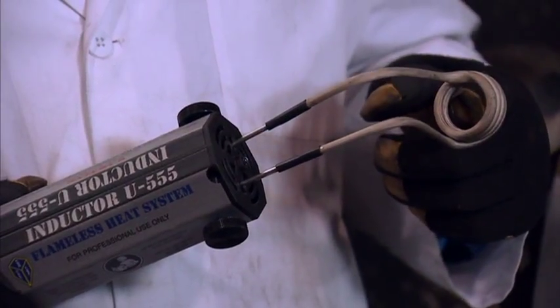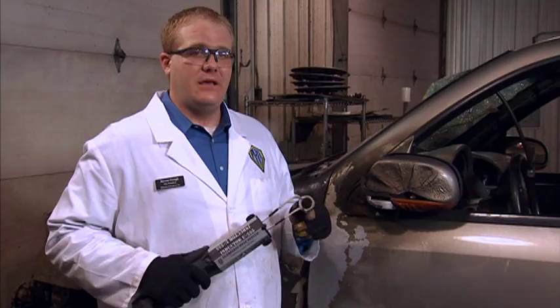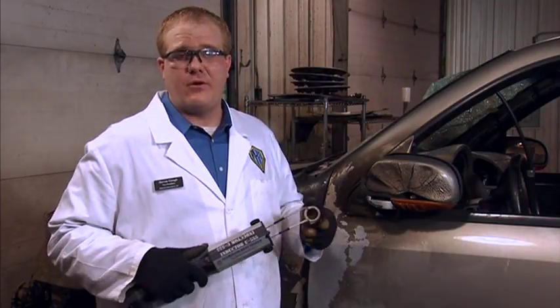The high-temperature fiberglass sleeving protects the coil from grounding out in the load being heated. If the insulation is breached, grounding out can occur, thus creating a spark. We now lose our advantage in flammable areas.